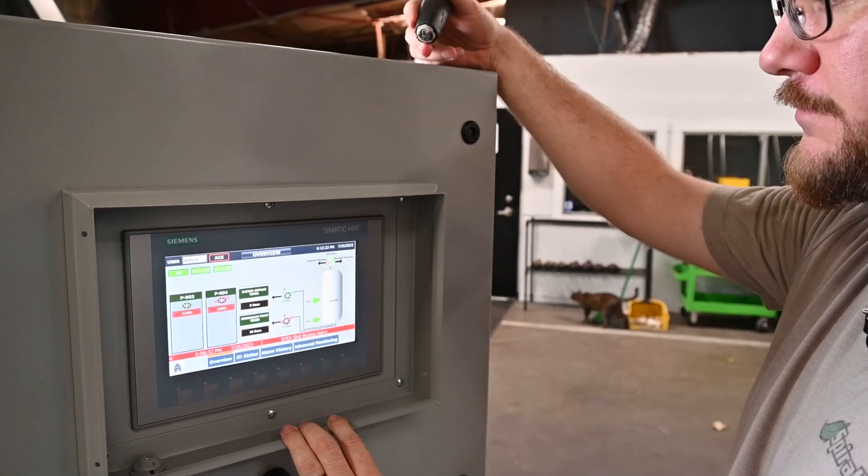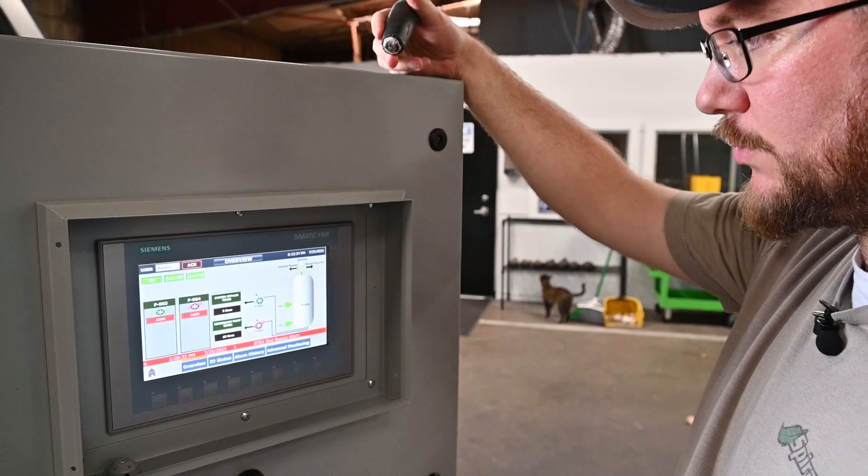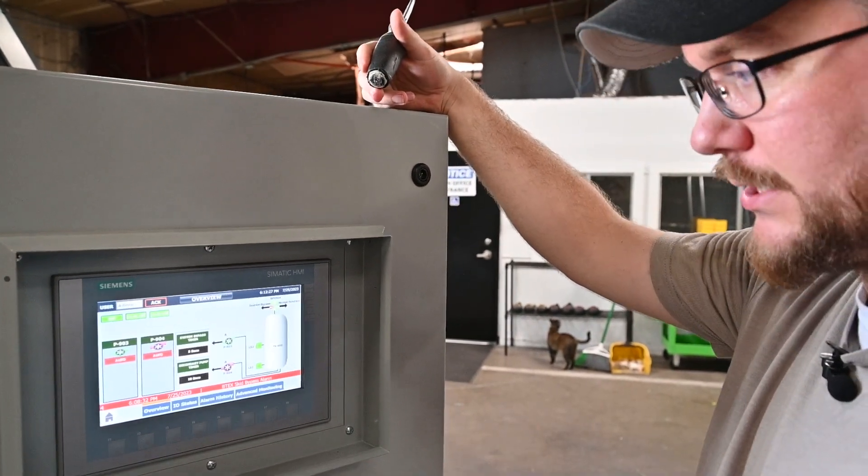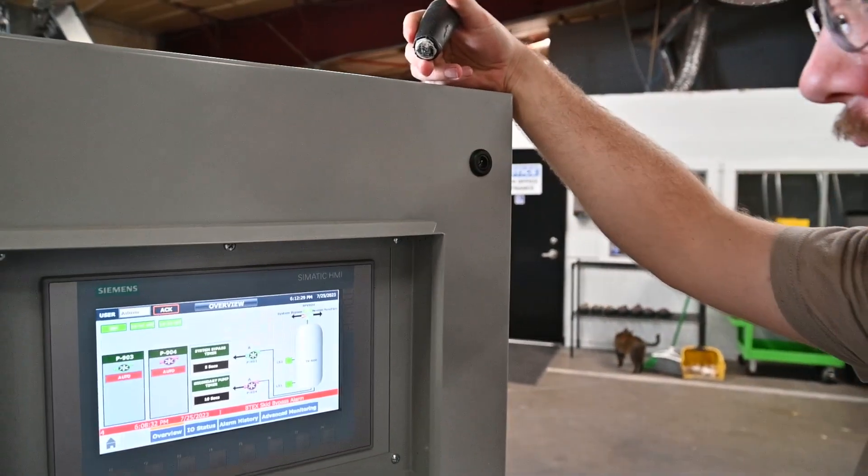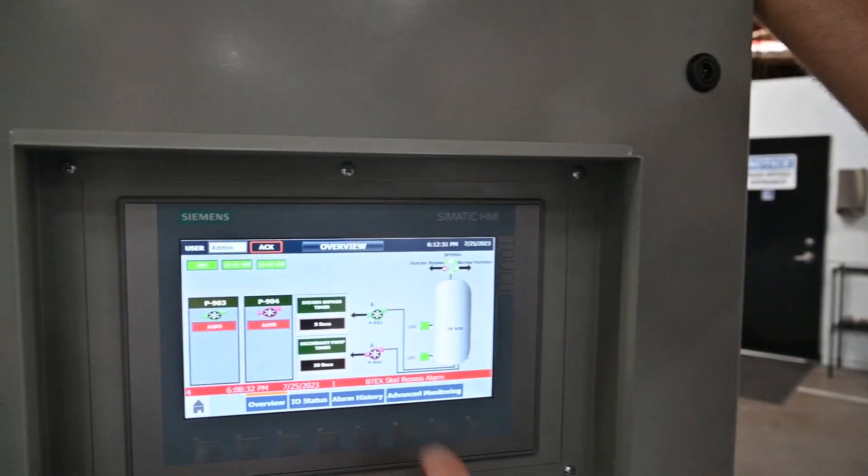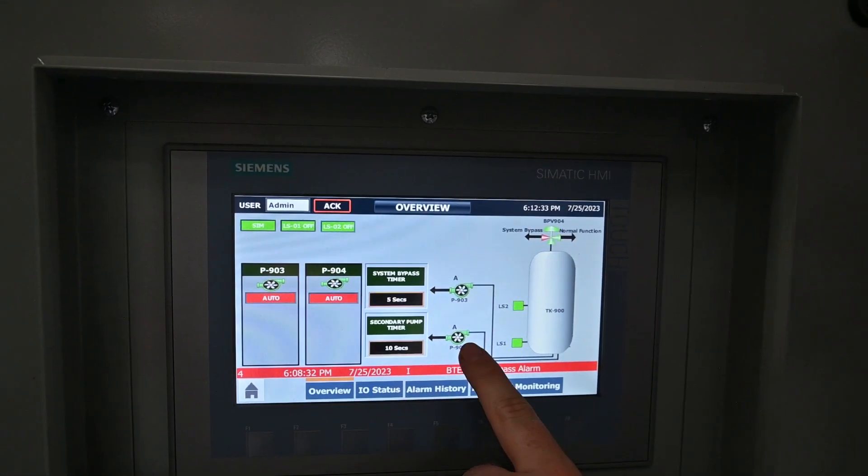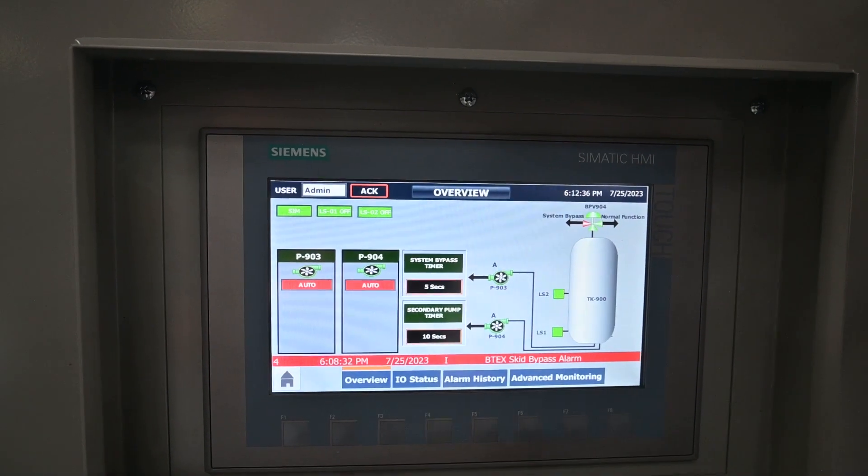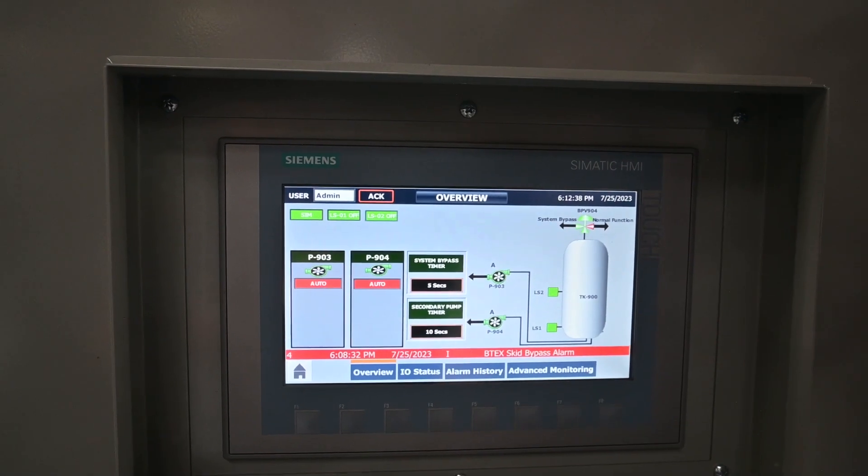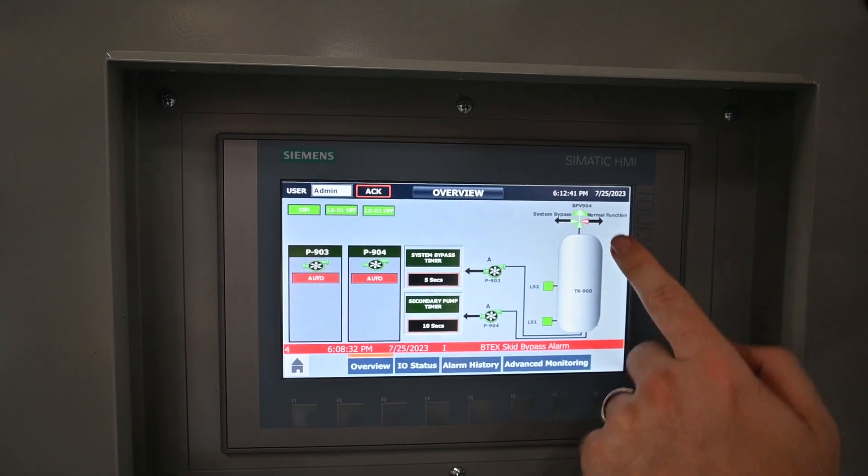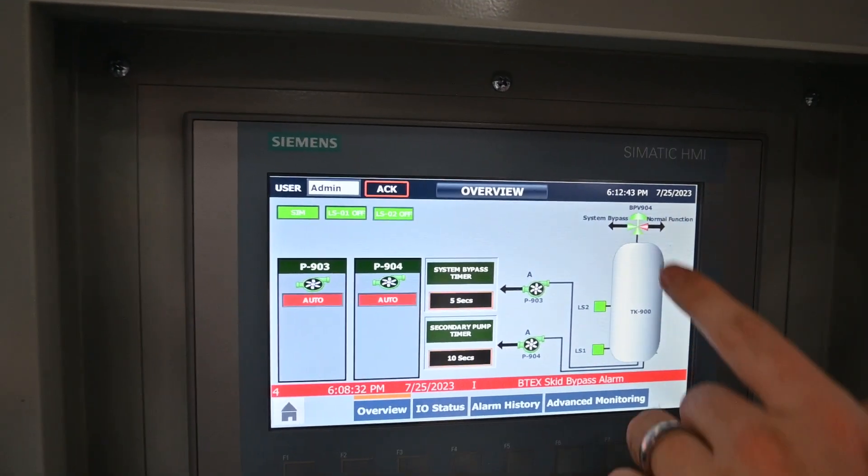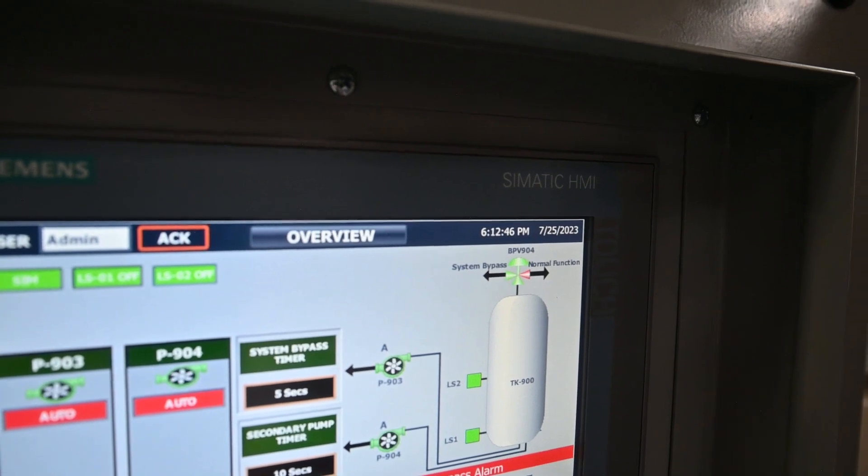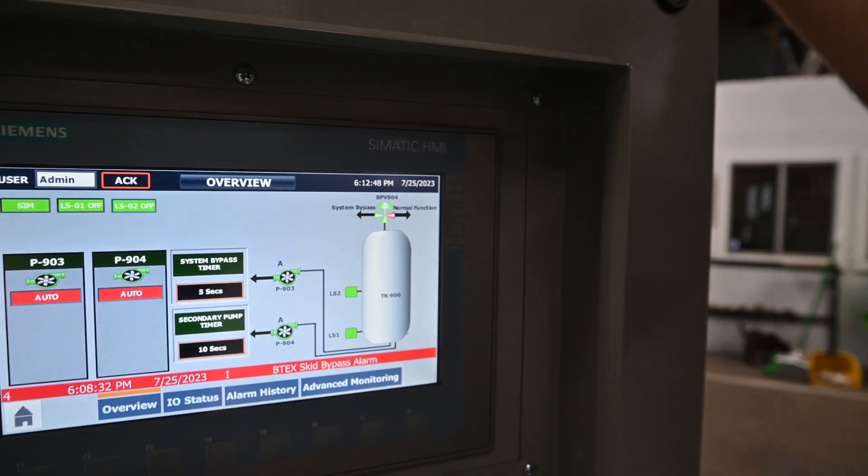Now, let's say something was wrong with the pump, or there's just way too much condensate being created, abnormal conditions. After 10 seconds, your backup pump kicks on like normal, then after an additional 5 seconds, if it is still not able to purge that liquid, it will send it into bypass. It has now been in system bypass, and you get BTEX skid bypass alarm.